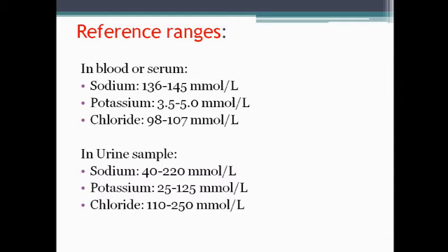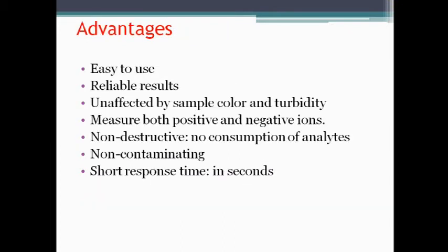So these are the ranges of the many electrolytes. The advantages of using ion selective electrode analyzers: they are easy to use, the results we get are reliable, and unaffected by sample color or turbidity.